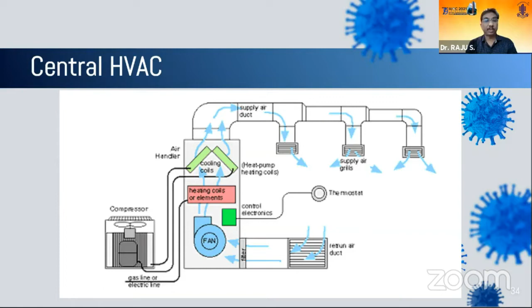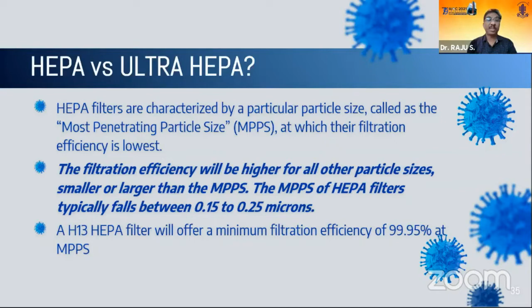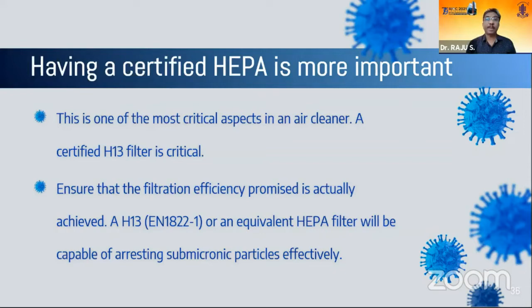Then the next question was HEPA versus ultra HEPA. This was also making the rounds when we were discussing last year. Again, it's very important to understand the concept of most penetrating particle size. The filtration efficiency will be higher for all particle sizes, either smaller or larger than the most penetrating particle size. The most penetrating particle size for HEPA filters typically falls between 0.15 and 0.25 microns. If anything is smaller than this, it will also be filtered efficiently by the HEPA filter. That is very important to understand, and this is the concept of the most penetrating particle size. So what is more important is to have a correct HEPA filter which is certified and is called a HEPA-certified filter.